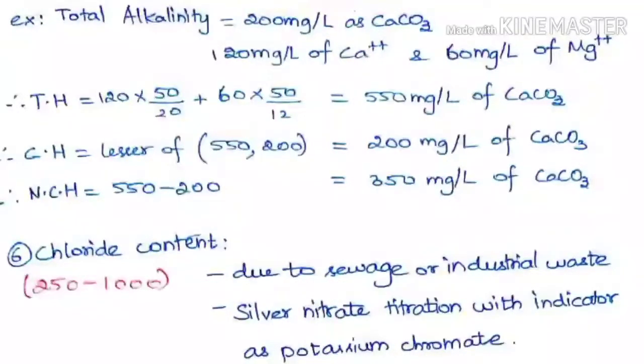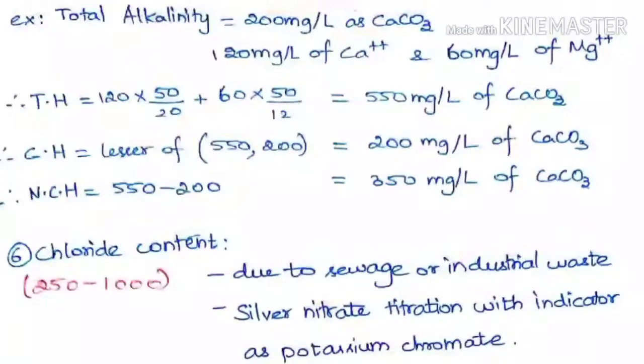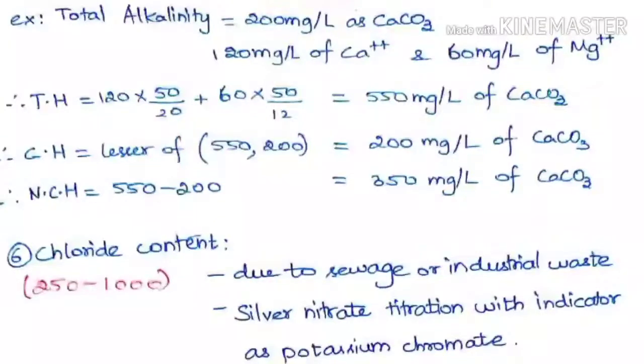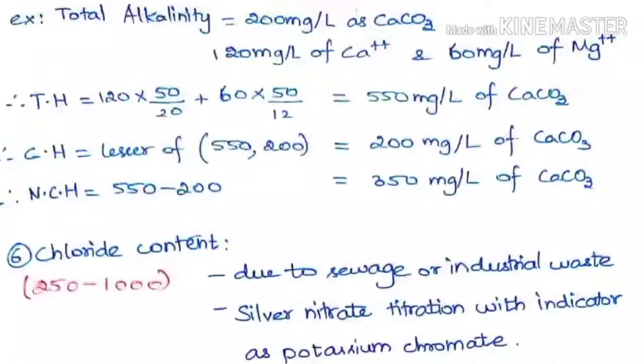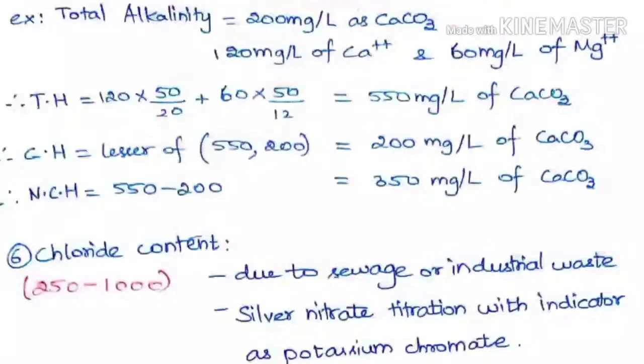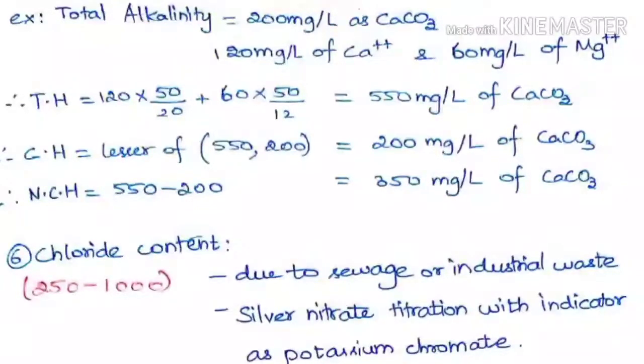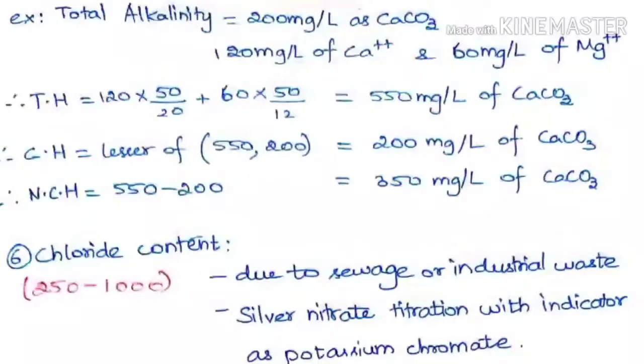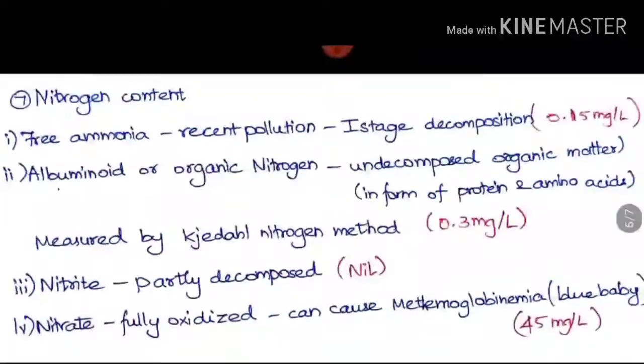The next characteristic is chloride content. The desirable limit per IS code is 250 ppm and the permissible limit is 1000 ppm. Chloride presence is due to sewage and industrial waste discharged into rivers. If chloride content is high in raw water, it indicates sewage mixing. Chloride is measured by silver nitrate titration with potassium chromate as the indicator.